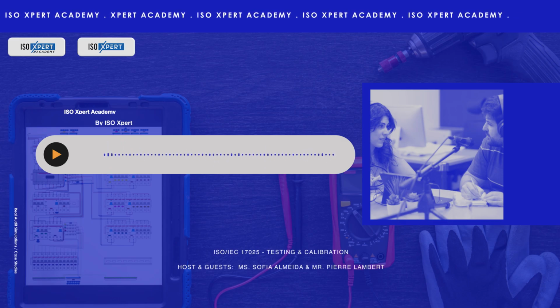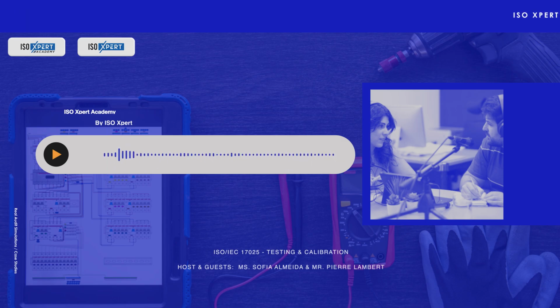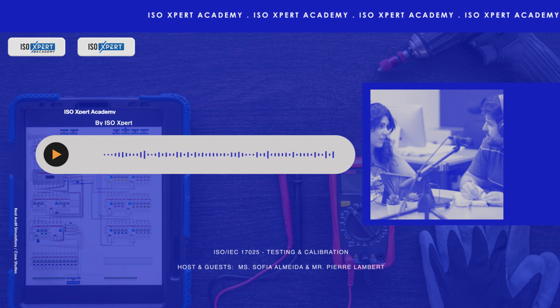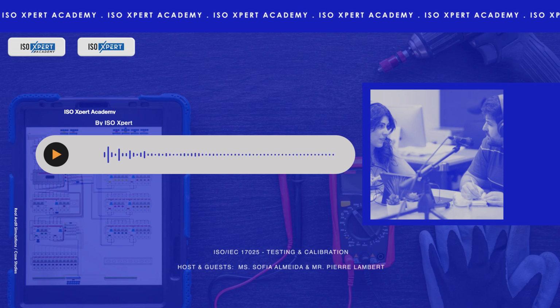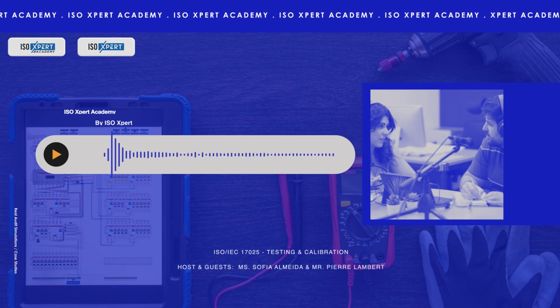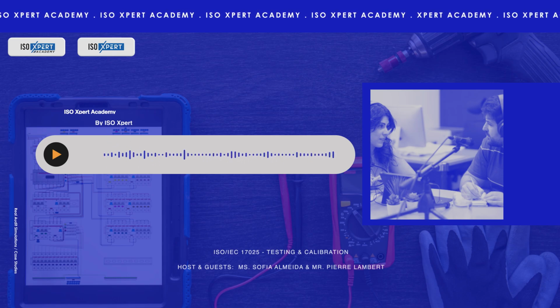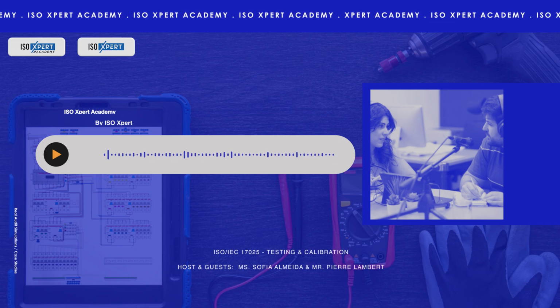Updated after what? After a recent change they'd made to the environmental controls in the lab, their calculations were still based on the old environmental conditions. So the temperature or humidity stability might have changed, but their uncertainty claims hadn't caught up. Precisely. The uncertainty files they were using had outdated values for things like environmental variance. That seems subtle, but potentially quite important. If the environment changed, the uncertainty probably changed too. It likely did. And it underscores how dynamic calibration needs to be. You can't just calculate uncertainty once and forget it. You have to maintain it, especially if conditions change. The action: recalculate the uncertainty with the new data and revise any reports that might have been affected.